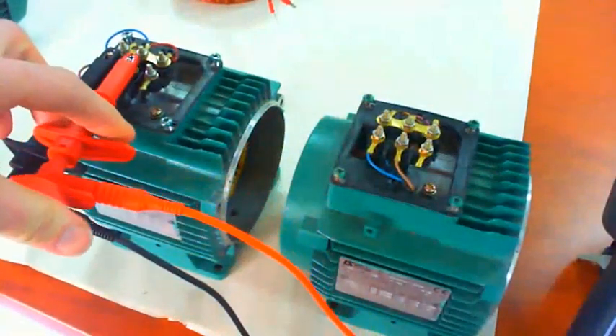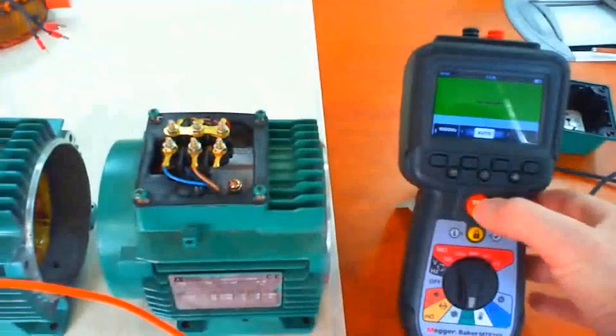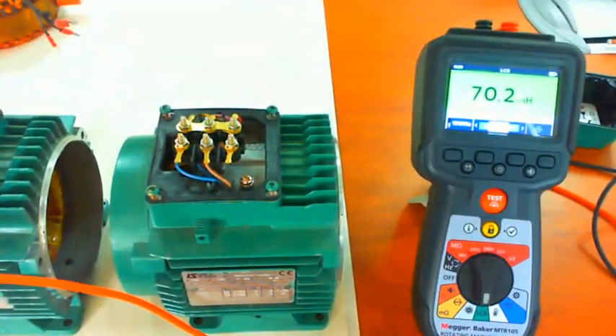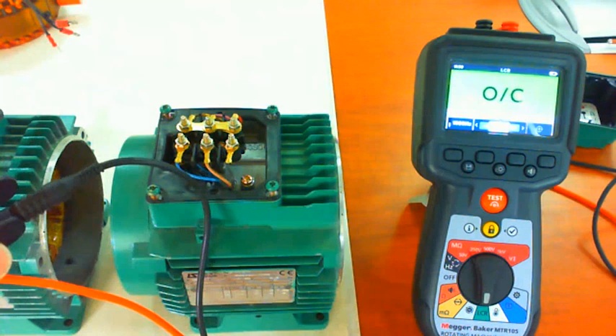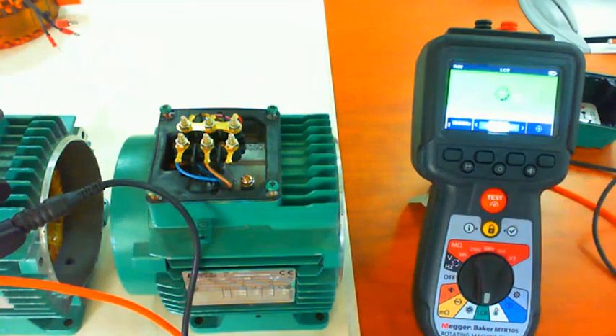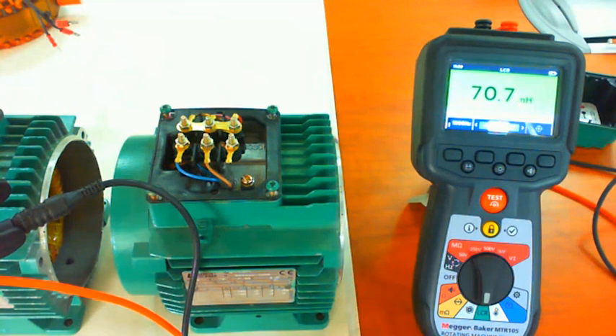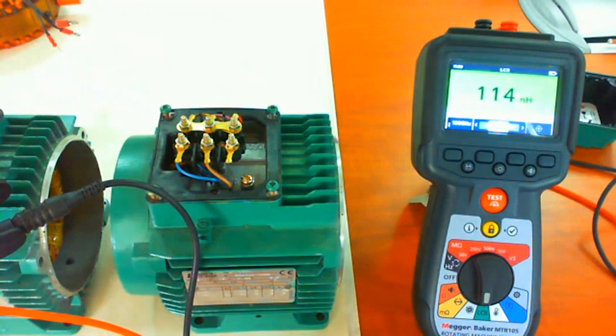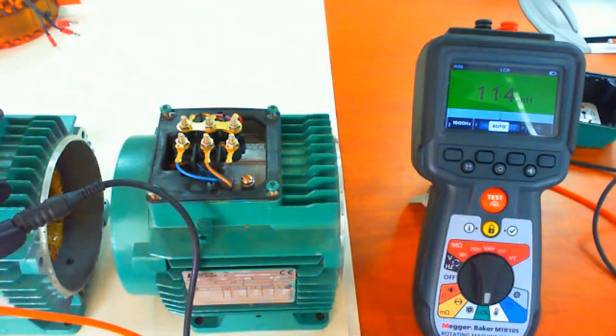I'm going to go across what effectively we think is L1 and L2. And I've got 70 millihenries compared to 114 or so. I go across WU. I've also got 70.7. And then I go across WU and I've got 114. So you can see that the two phases, which I've swapped over, blue and pink, gave us those different values of 70 millihenries, where it should be around 114, 115. So clearly, inductance can tell us when we have a winding connection issue.